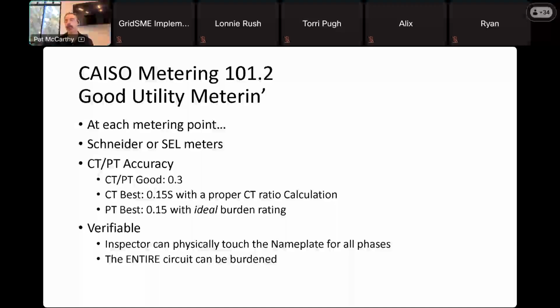There is a calculation to do so. And while CAISO may not have a requirement that you do that calculation, many utilities are starting to bring that requirement on board. So again, back to the Venn diagram, you need to meet all requirements. You're going to have to do some math before throwing CTs around in your bus arrangement. I'm specifically mentioning this because a lot of design engineers and design firms are protection and control focused, and the CT consideration for a protective device is completely the opposite of a metering device. So I very often have to chime in with recommendations and assistance on how to accurately capture the current that's being used to measure settlement energy for a project.